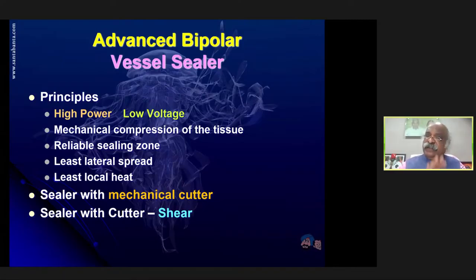I was just telling the engineers of the different companies, long back, 10 years back, why are you not using this current? You have an auto-sensing device, you have an electrosurgical generator which can modulate current. So you know the sealing is complete. After sealing is completed, coagulation is complete, it jumps from coagulation mode to the cutting mode and automatically the cut occurs. This machine senses that. But they were afraid that the sealing, by cutting, may not be appropriate. They are working on it. Still they are working on it.